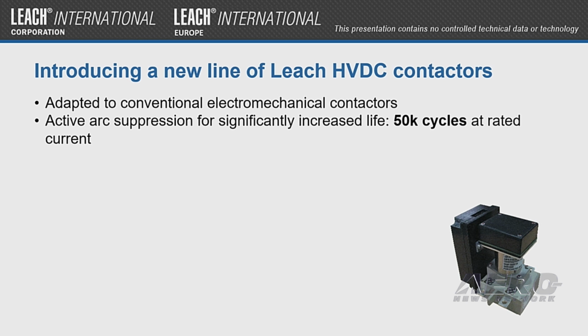This is going to enable new levels of reliability for high voltage systems. In the past, you always had a zero cross on the contactor to extinguish the arc across the contacts. There's a few technologies out today that allow for arc suppression for high voltage, but we have a novel patented solution for that. This is going to enable us to have the same reliability for our high voltage DC contactors as what we've always had for AC contactors, which is new for the industry.